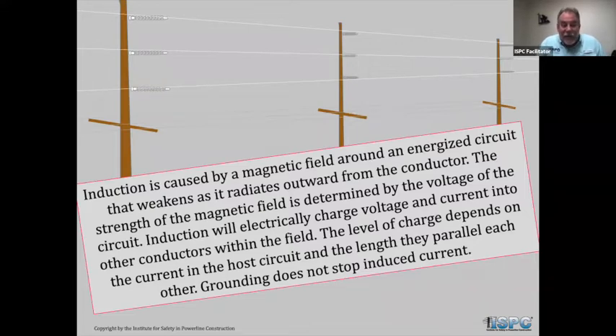It's usually, I say usually grounded because things happen out in the field. People steal copper and things like that. So they're usually grounded, which dissipates the voltage off of it, but the current is still flowing into the earth. If you can get it at a different potential, you might receive a shock.